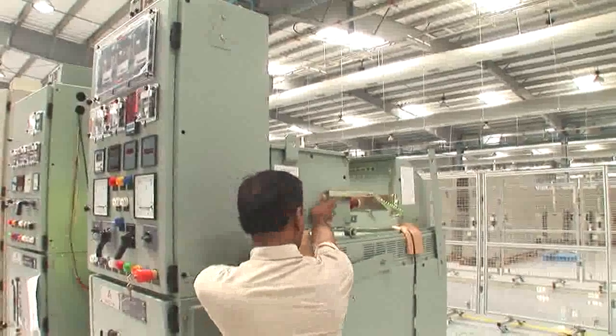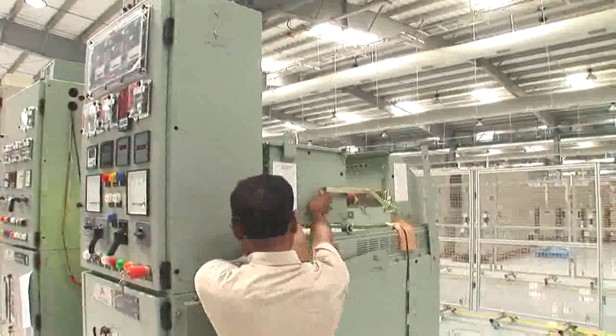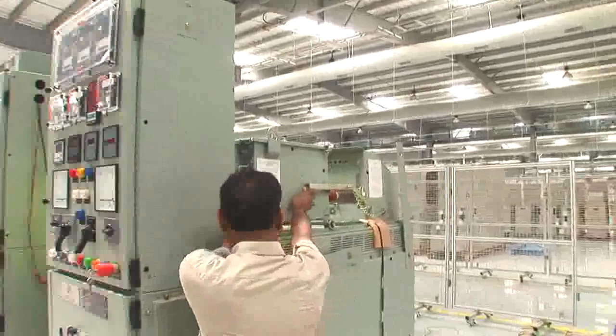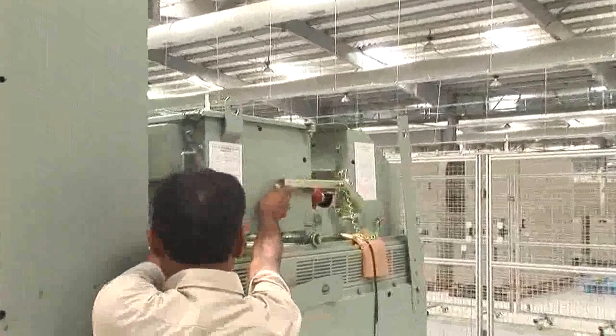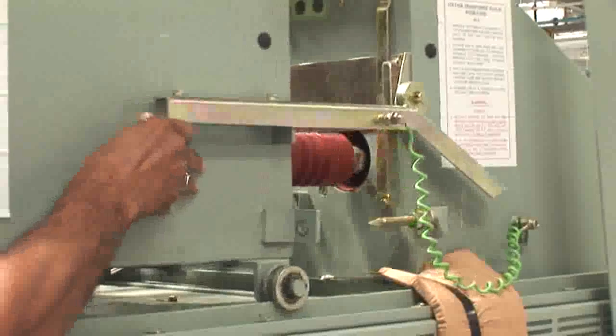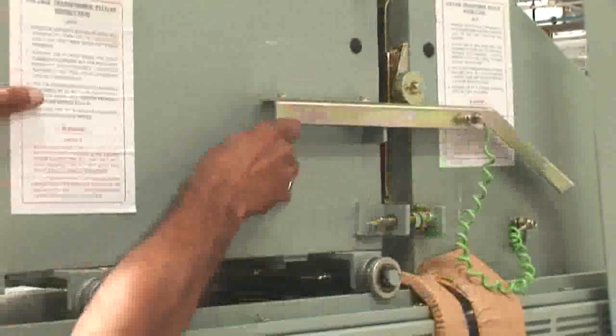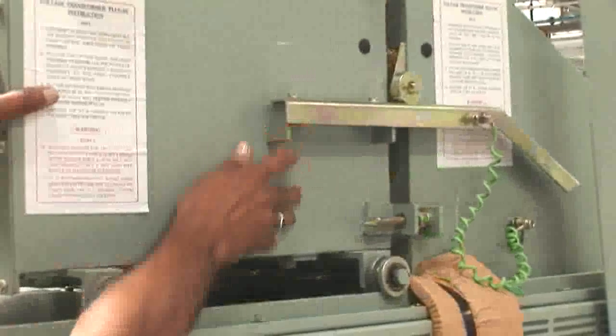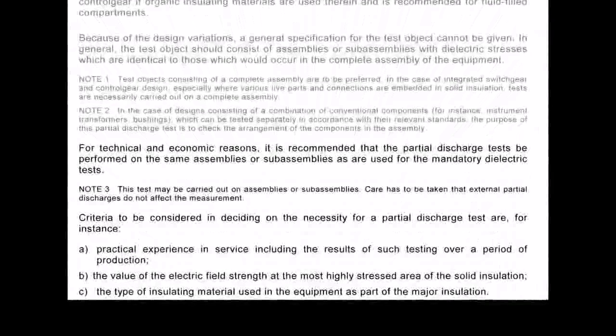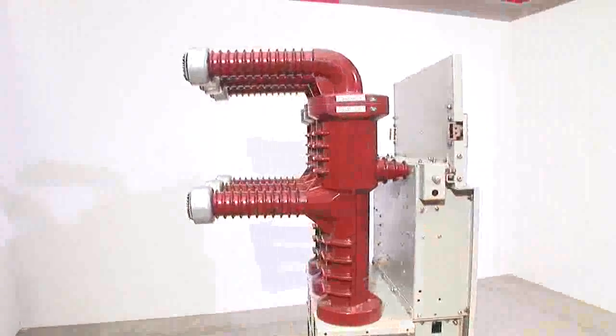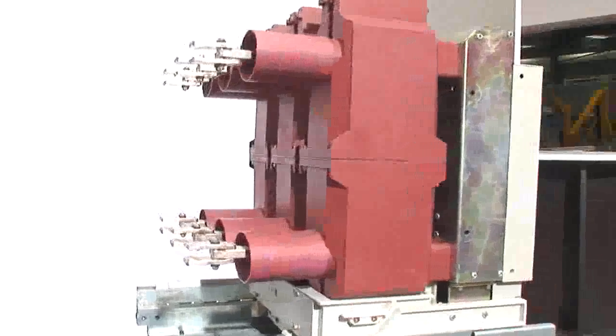The real-life simulation also means that a potential transformer on top of the cubicle could not be used unless it's proven safe, by performing the internal arc test with the transformers at the top and a dummy operator in the operating position. Another example of the changes towards better safety and reliability is that the partial discharge test has been recommended for the sub-assemblies and not only for the individual parts, as was the case with the last IEC. This means that it's not the individual performance of the component but the whole sub-assembly which matters, as it really does in real-life working conditions.